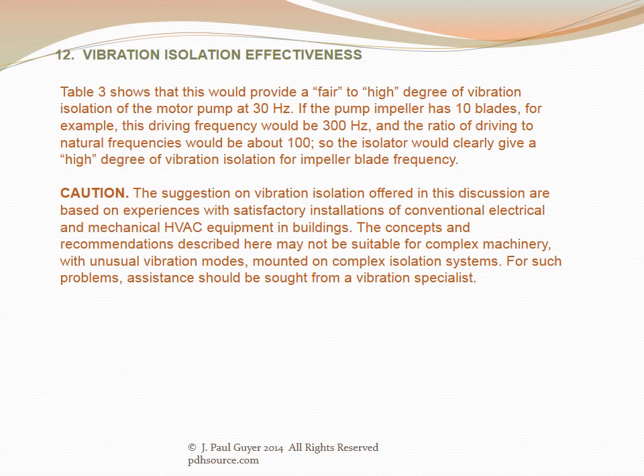An example: an 1800 RPM motor pump unit on steel springs with 1-inch static deflection has a driving frequency of 30 Hz and a natural frequency of 3 Hz, giving a frequency ratio of about 10 — providing fair to high vibration isolation at 30 Hz. If the pump impeller has 10 blades, the driving frequency is 300 Hz with a ratio of about 100, giving high isolation for blade frequency. Caution: these recommendations apply to conventional HVAC equipment; for complex machinery with unusual vibration modes, assistance from a vibration specialist should be sought.